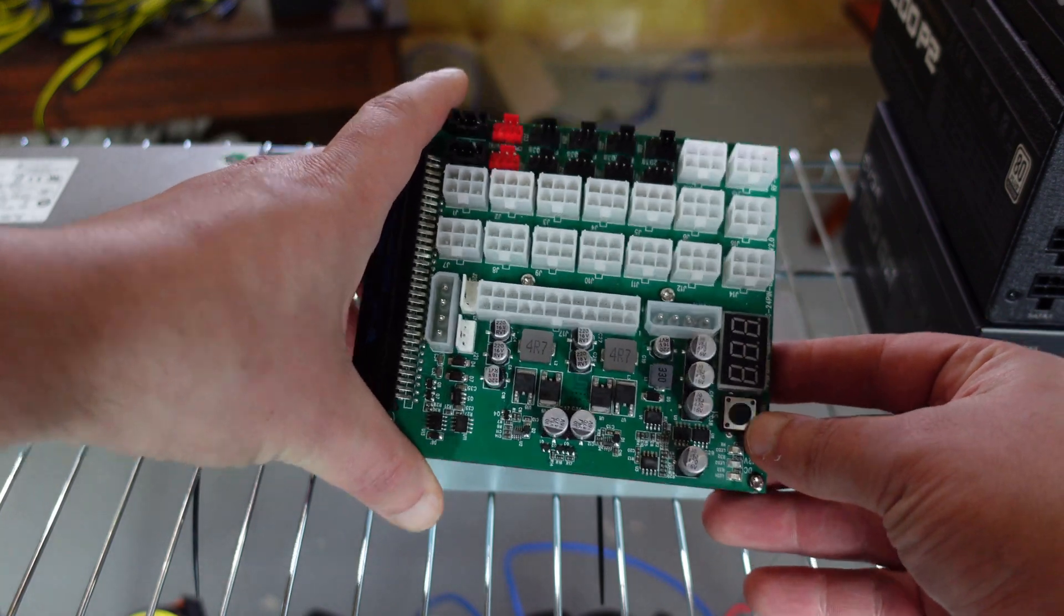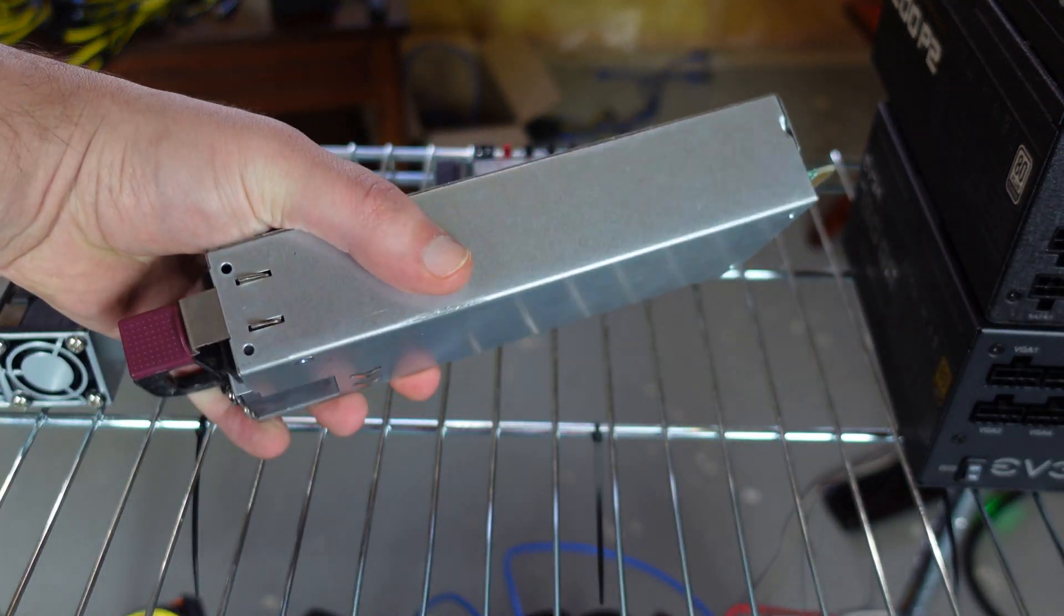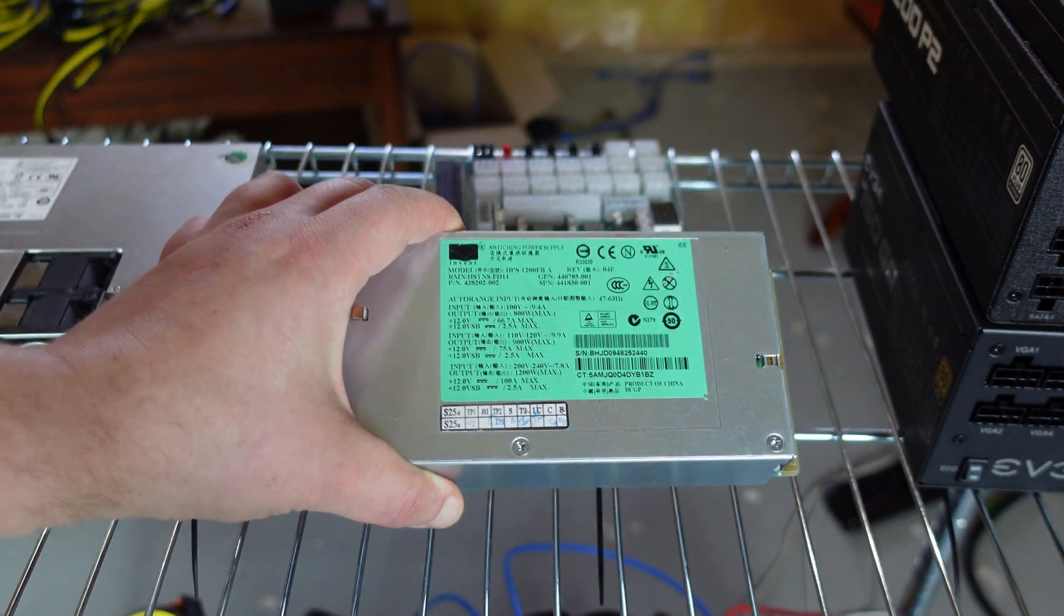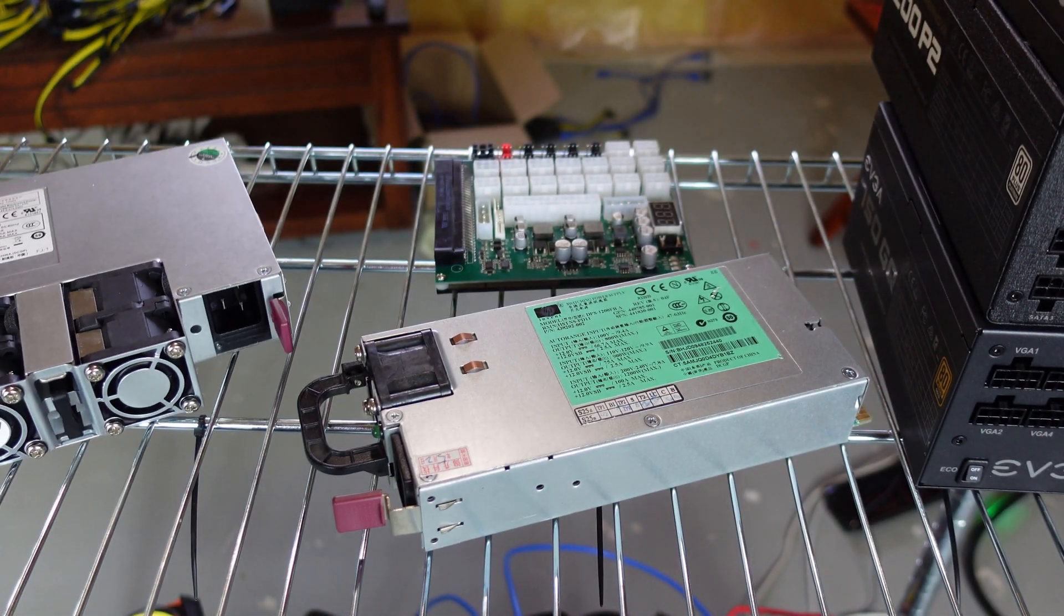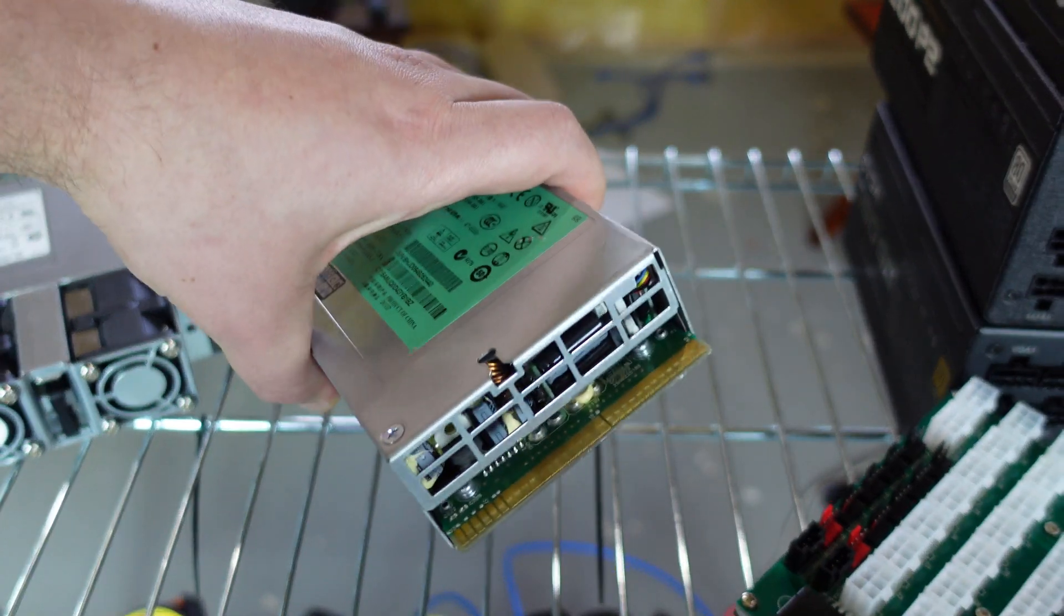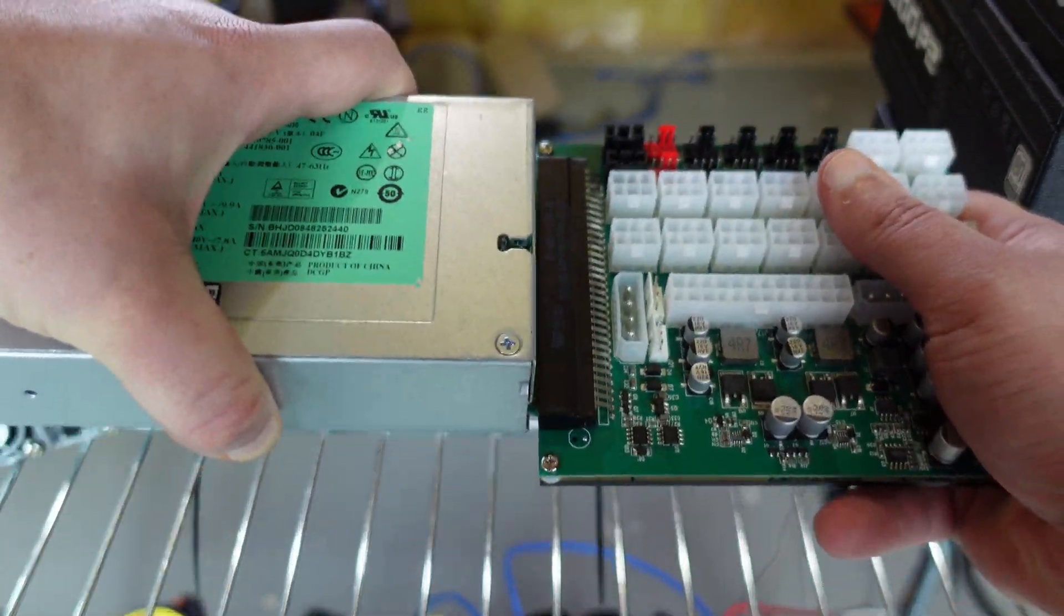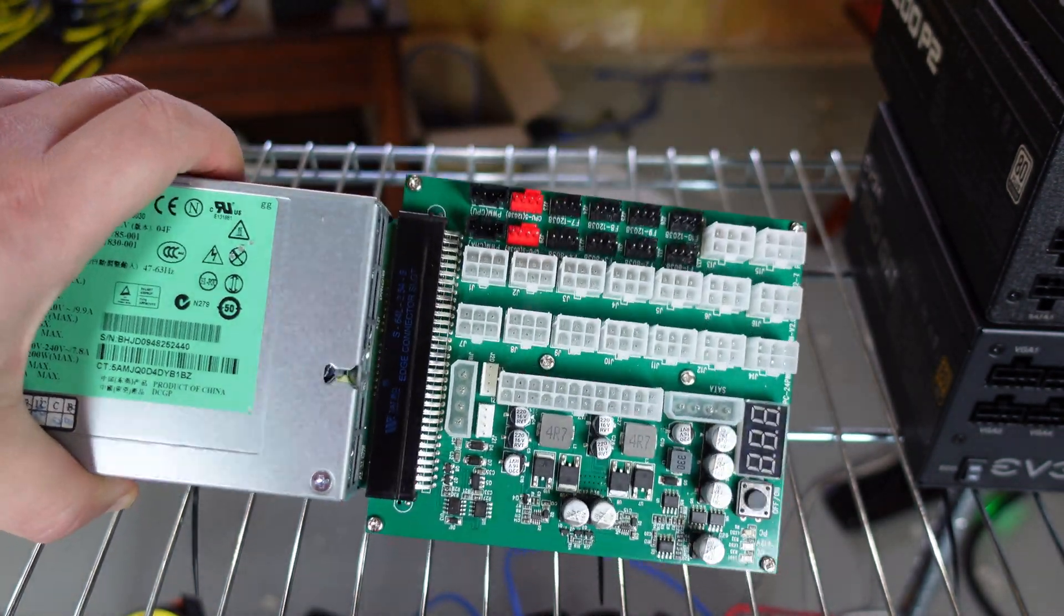Now we're going to look at how to install this. Basic installation: first you're going to need an HP server power supply, like this 1200 watt on 240 and 900 watt on 120, or this 2400 watt but only on 240. Installation is quite simple. We've got some pins and they will line up with these pins here, so we'll just line them up and push them in. Boom, we are installed onto our server power supply.